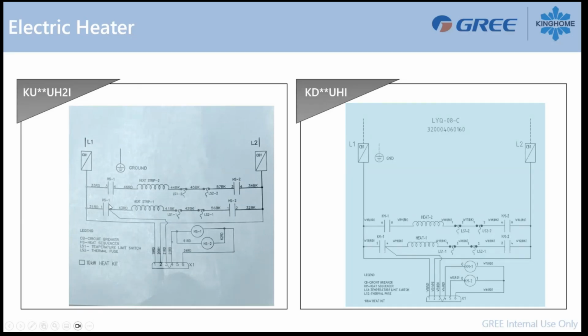We have also, if you take a look here at HS1, terminal 2, you have a small wire here going back on the quick connection plug. This is a feedback signal on the main board to tell the air handler that the contact is closed. So we have voltage here coming to the heat strip, so my heat strip is on. So this little guy here is a feedback to the board. So 1, 2, 3 is your high voltage connection. And there's 4 and 6 here for a low voltage control. That will be your 24 volt from W2 aux. We'll send out 24 volt here to the coil on HS1 and HS2, and then going back on the common.